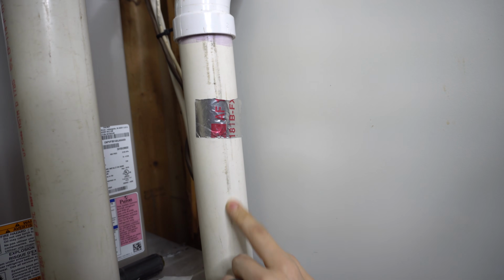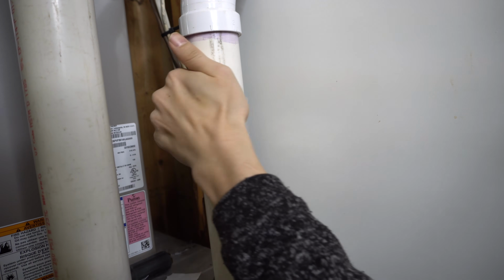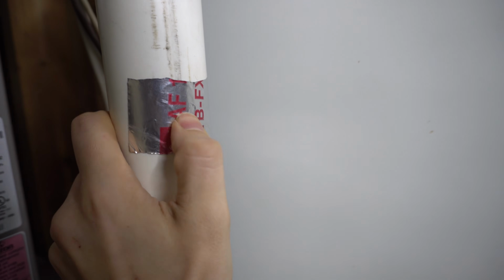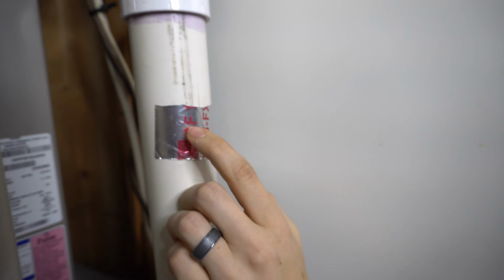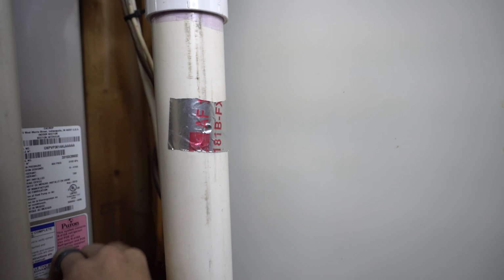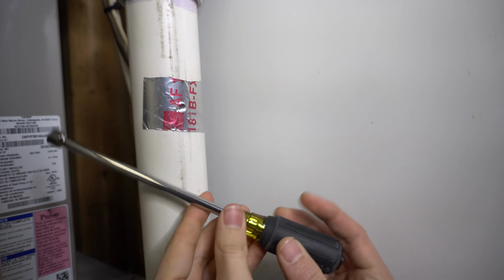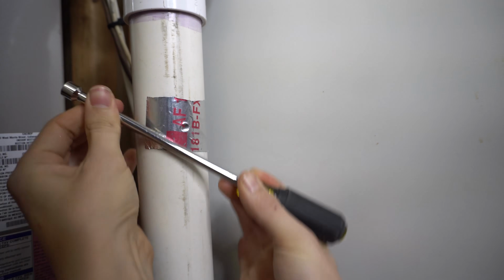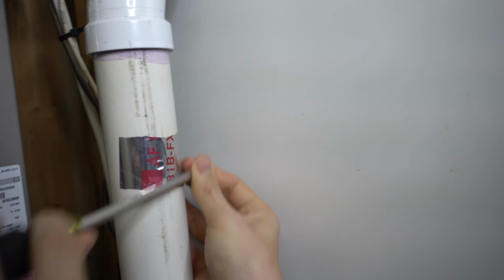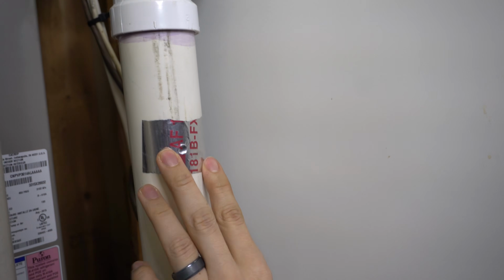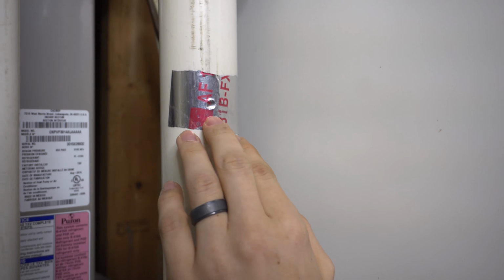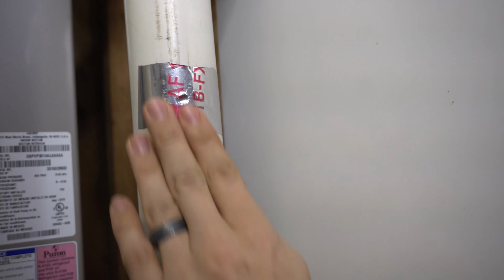Then of course you're going to have streaks of water coming down because it's on really sloppy. What I like to do is put it on and then press down into the hole, wherever the hole was. I make sure that the hole is really nicely sealed, so you can see the outline of it all the way around. After that, it's neat, plus it's a very good seal. I take a nut driver and rub on it on all sides like that, so it completely sticks to the PVC pipe and makes a good seal. If you do this, even if the sheet metal tape dries out and becomes brittle, it's not going to leak anything through. At least I've never seen it leak. When you have it sealed up this nicely, that's really all you need to seal up that hole.